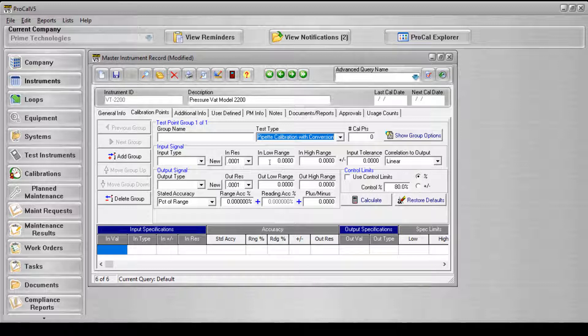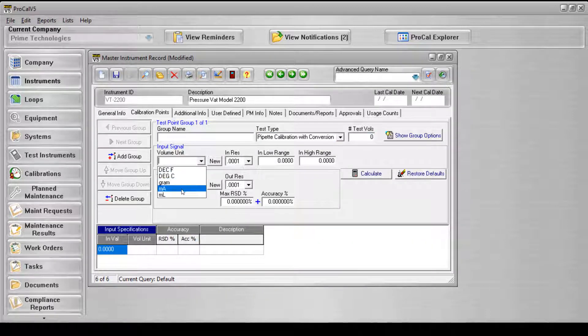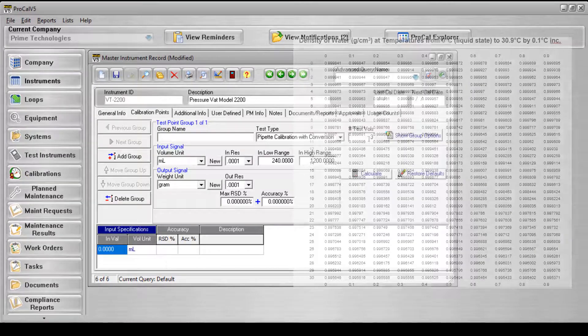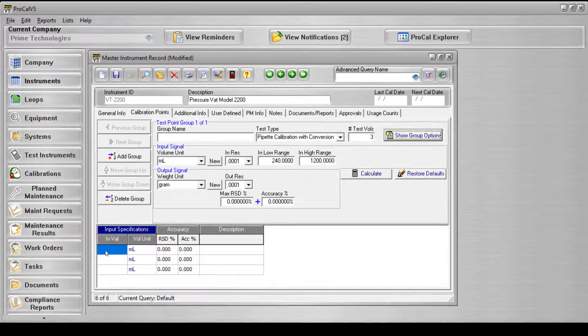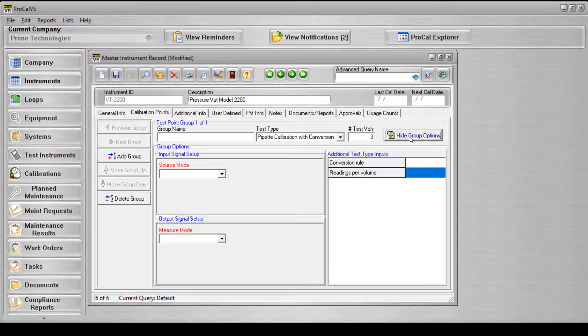After the test type has been selected, the field names will change according to the settings defined by the file. During calibration, a water density table is utilized for the conversion calculations. This pipette test type will test the accuracy in each reading and the relative standard deviation percentage for each test volume. The test type inputs used in this test are found in the additional test type input section, which can be accessed by clicking the Show Group Options button on the right side of the screen.